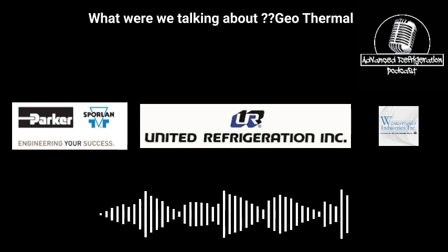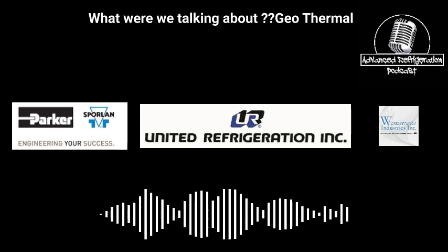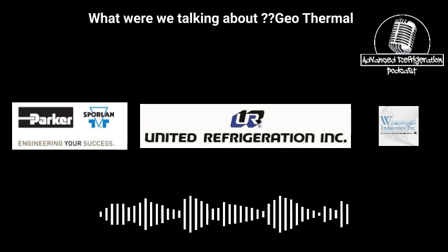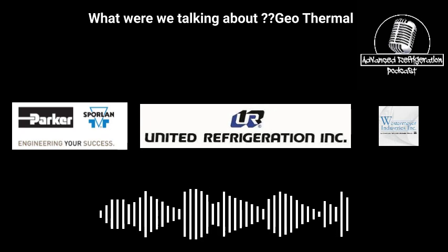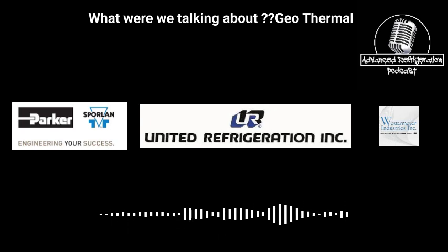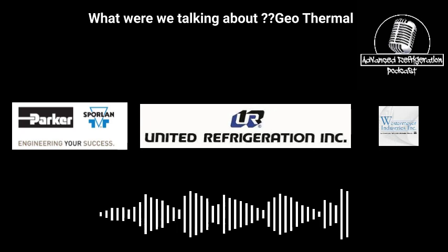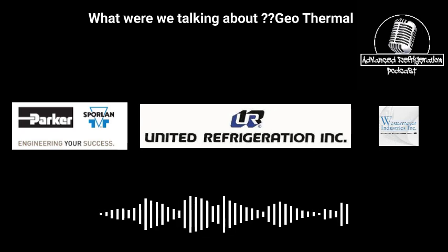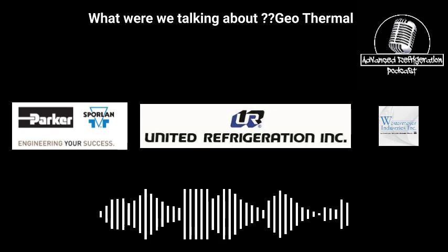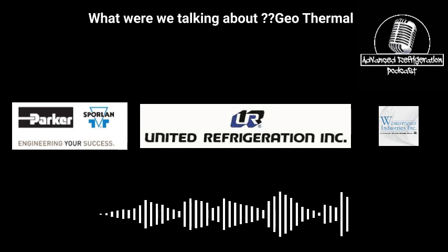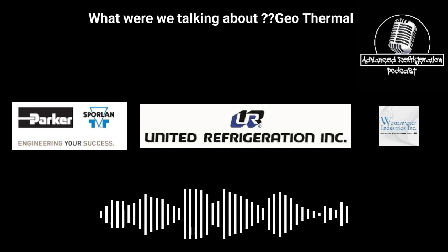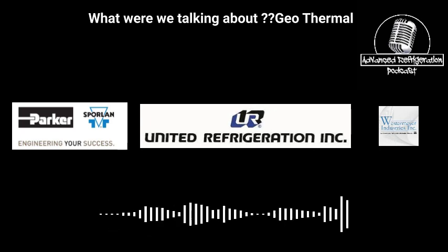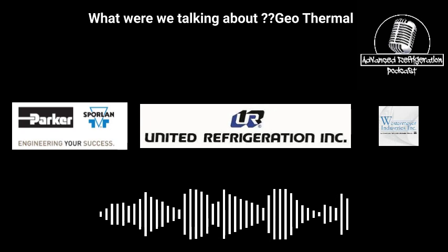So what is geothermal? There's a couple of different ways of doing this. There's heat recovery stores and there's geothermal. Geothermal would be using ground loop water to cool and heat the store simultaneously. Hold on. Are they using it just for actual conditioning, or are they using it for condenser water? In the summertime, it would be condenser water. Uh-huh. In the wintertime, it would be your heat source. And a condensing loop then, right?